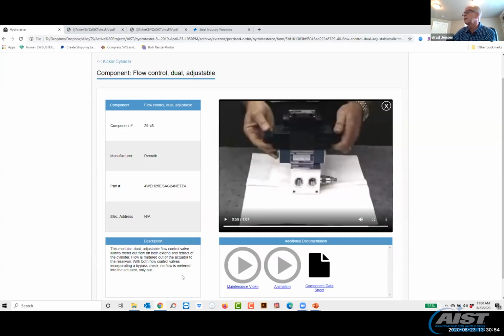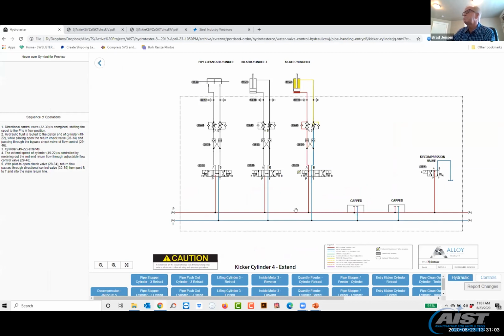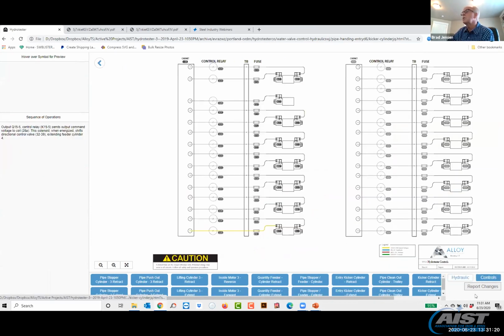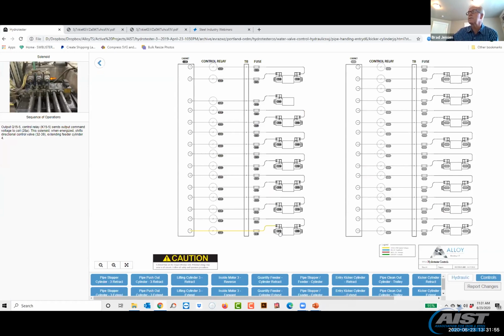Go back, and again, we've got component data. And maybe that's not the problem, maybe that doesn't solve it. We go back to the coil, and we find out that the coil is good. It tests out fine. But wouldn't it be nice to very quickly jump over to controls and see if everything is fine there, or where the IO addressing is. I know that if the coil is fine, and I go back to the cabinet and all the permissives have been met, then it may just be a wire connection, or in this case, a fuse. But how nice is it to roll over and see, okay, that's the coil that gives me an extension.